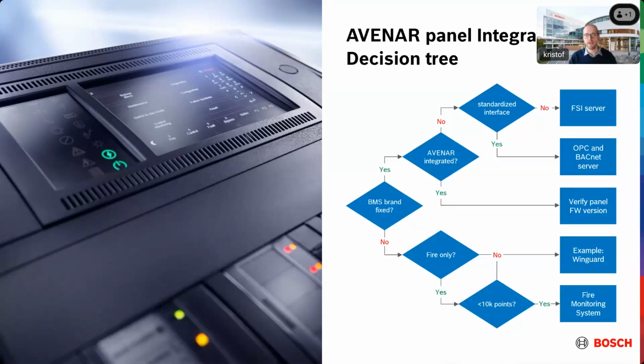Okay, so now looking at the complete decision tree. First question: is the building management system brand fixed? If yes, then ask yourself, is AVENAR already integrated in this building management system? If not, we need to check, does the customer require a standardized interface? If not, we recommend using the FSI server because this is the most direct way to connect to the AVENAR panel. If you need a standardized interface, we have two options: OPC and BACnet. OPC is more often used for building integration systems and SCADA systems, while BACnet server is more appropriate for real building management systems.